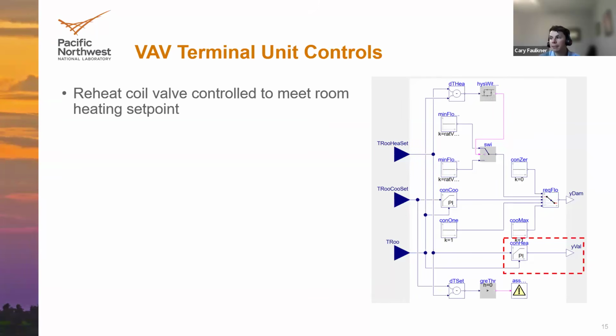for the PI block. And then, it depends on the specified control of these systems, but oftentimes the airflow from the system, from the VAV terminal unit to the zone is constant during heating, and then you just modulate the discharge air temperature using the reheat coil to meet the heating demand at the zones. But there's also other controls that might modulate both the airflow and the discharge air temperature for heating to meet the zones. I think in this case, it uses a constant airflow set point during heating.